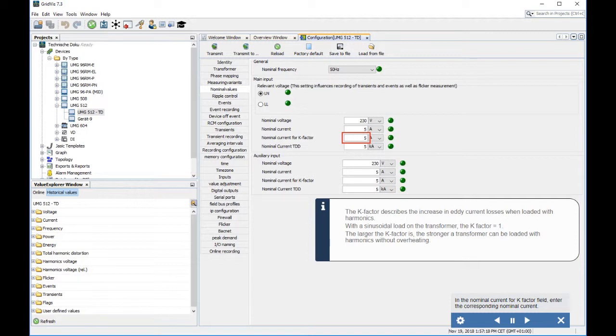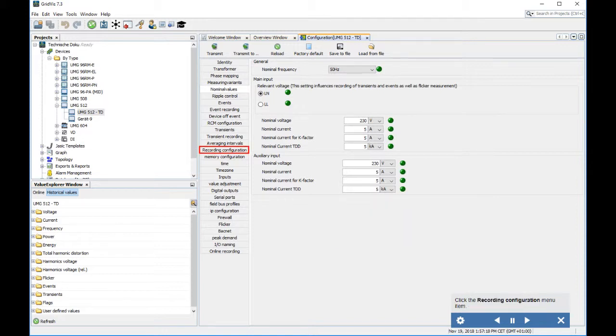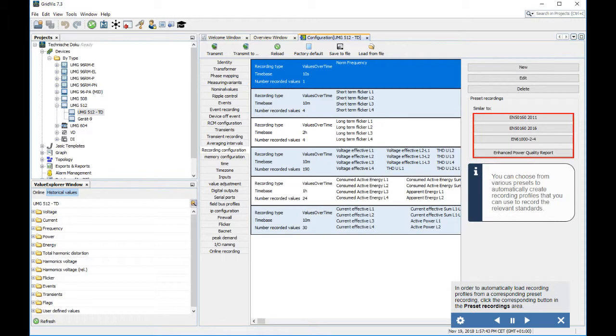In the nominal current for K-factor field, enter the corresponding nominal current. TDD (Total Demand Distortion) indicates the ratio between the current harmonics THD and the effective current value at full load. Enter the corresponding nominal current in the nominal current TDD input field, then click the Recording Configuration menu item.